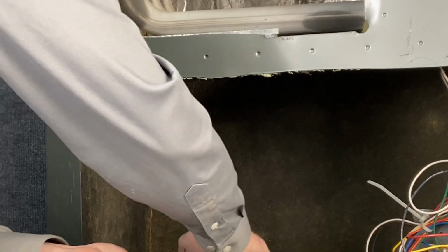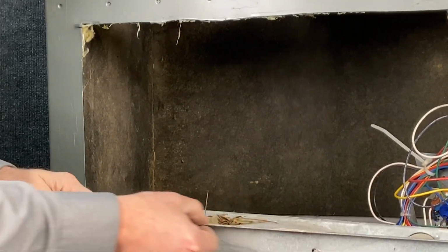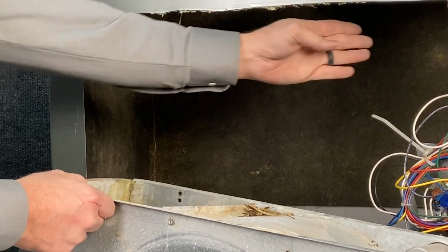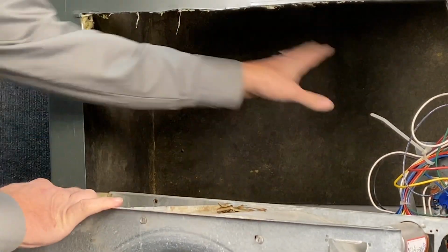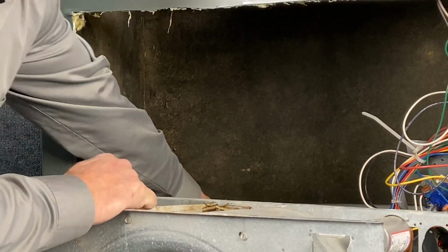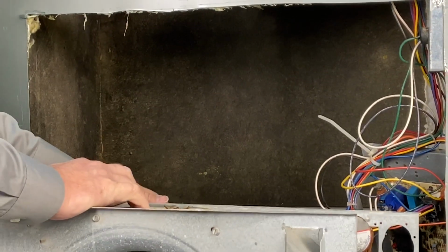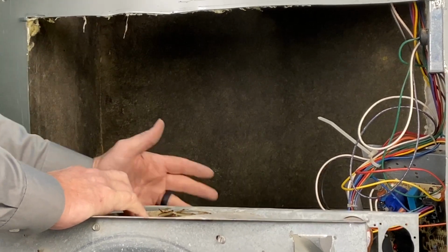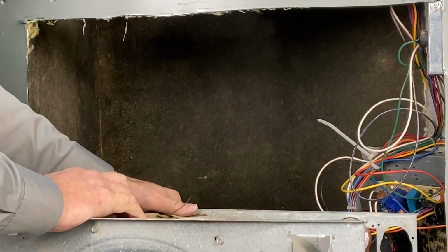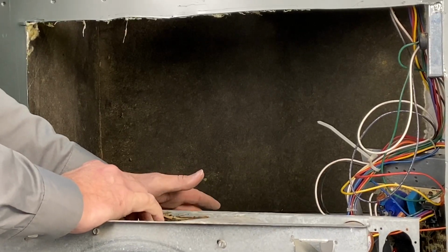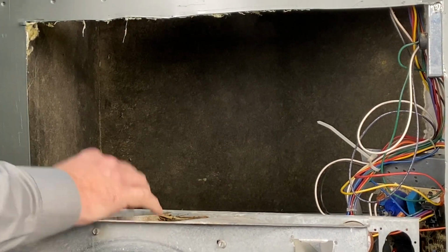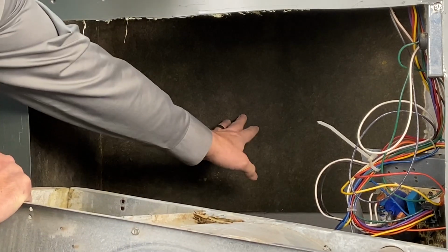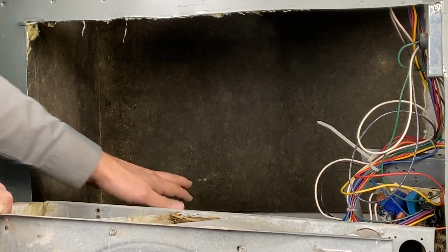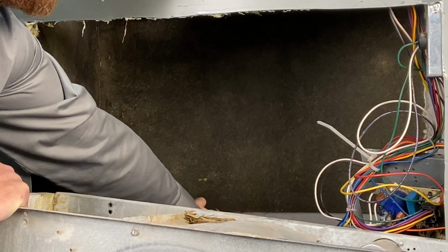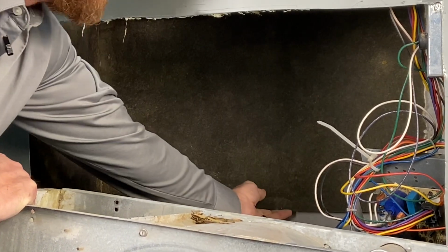If you can see now, this blower slid in these little tracks that are mounted up inside of here. It slides in, and this housing here needs to be cleaned as well. In this case, we have leaves in here, but there's going to be all kinds of dust and everything else that went through the filter, or improper filters, or if the case the customer didn't change the filter often enough. So this is going to be some issues. But also notice the insulation inside of this housing. I keep a shop vac so I can vacuum that out, but there's also a metal piece here on the sides, and it's only ½ an inch of insulation.